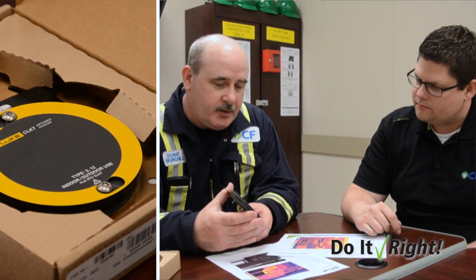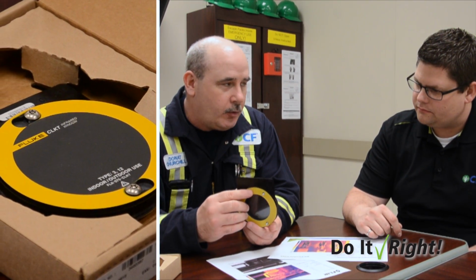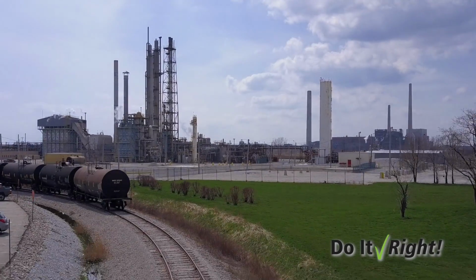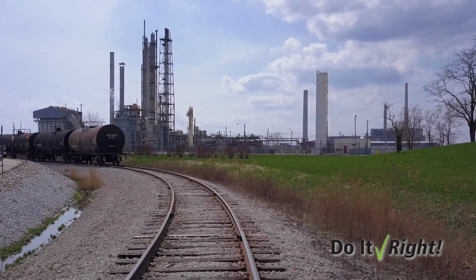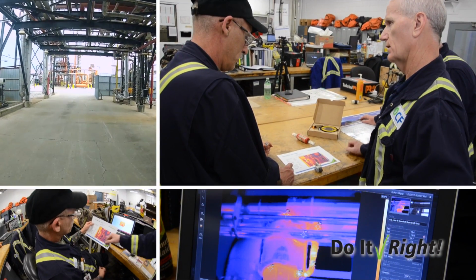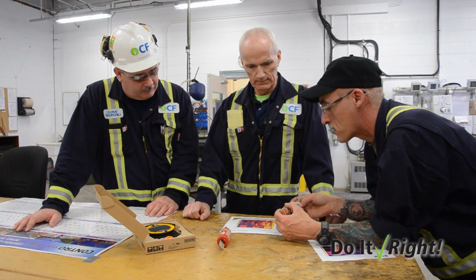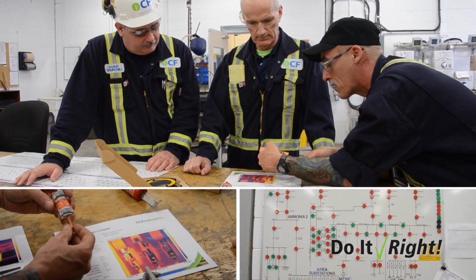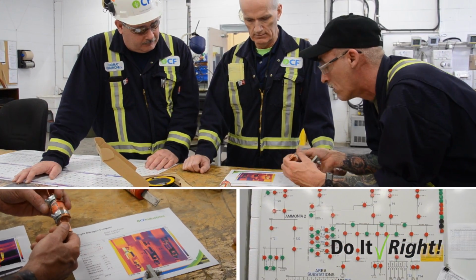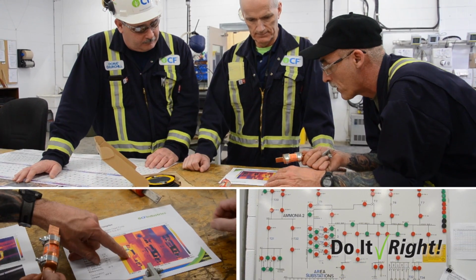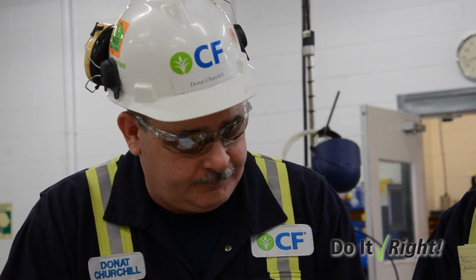We also didn't know that the newer cameras were in the market. We were doing IR scans with an older technology camera through a vendor. Everything about it is making the whole job much easier. This gives us an opportunity now to monitor electrical equipment even more frequently. We can go back and say, okay, what did that piece of equipment look like 5 years ago? Is this a similar condition to what we've seen before? And if it is, that helps us understand what we're going to have to do for repair when we take an outage. The IR scan windows was a very low-cost risk reduction activity.